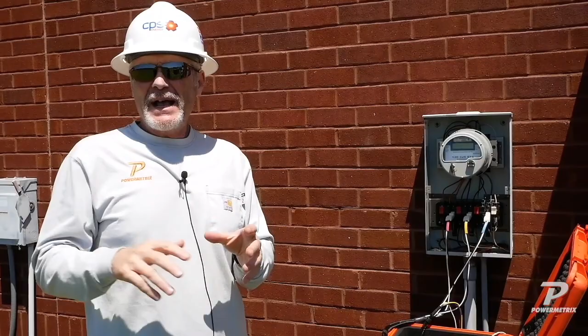We noticed that after we cleaned everything, it dropped from 10 to 5. It got a little bit lower, but it still wasn't below our 3%, which this test kit is set up for as a pass. We started getting down into the 4s and then the high 3s, so we're still going in the right direction. That's telling us we're probably on the right track. It's a corrosion issue, which we love, rather than having to go in there and change that CT out.